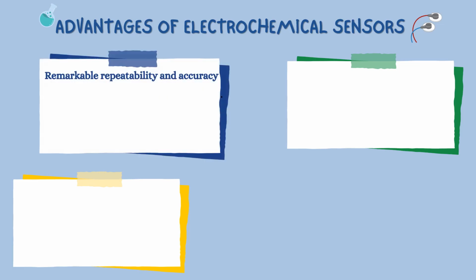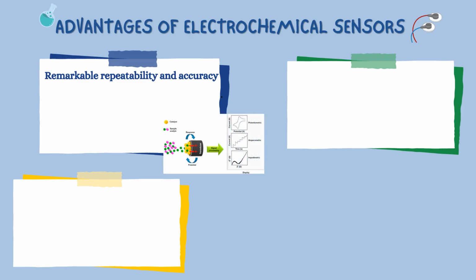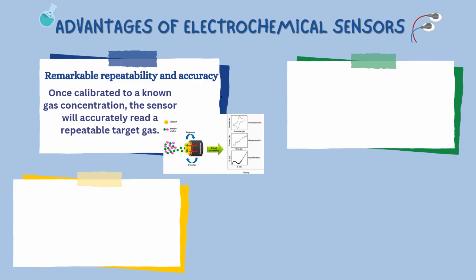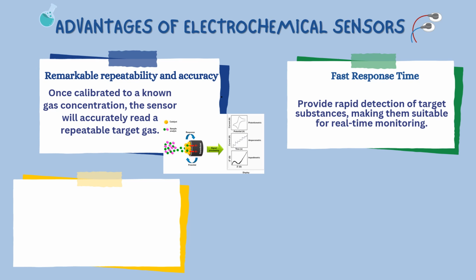Next, I would like to explain the advantages of electrochemical sensors. The first advantage is remarkable repeatability and accuracy. This means that when gas enters the transducer, the known gas concentration can be calibrated and the electrochemical sensor can accurately measure the same gas repeatedly. So this makes the electrochemical sensor dependable for monitoring the gas level in various applications. Second is fast response time. Electrochemical sensors provide rapid detection of target substances, normally within seconds, making them suitable for real-time monitoring.